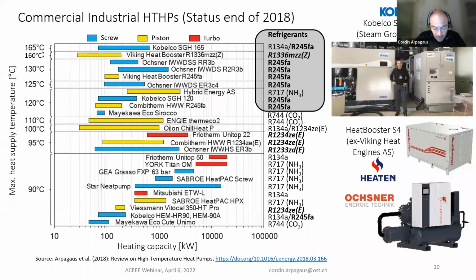This slide shows a variety of products available on the market. On the left, a graph shows on the y-axis the maximum heat supply temperature as a function of the heating capacity of the heat pump, in logarithmic scale, with 1000 kilowatts (1 megawatt) in the middle. The colors represent different compressor types: yellow is piston, blue is screw, and red is turbo compressors. Brand names are listed, and you can see it goes up to 165 degrees.